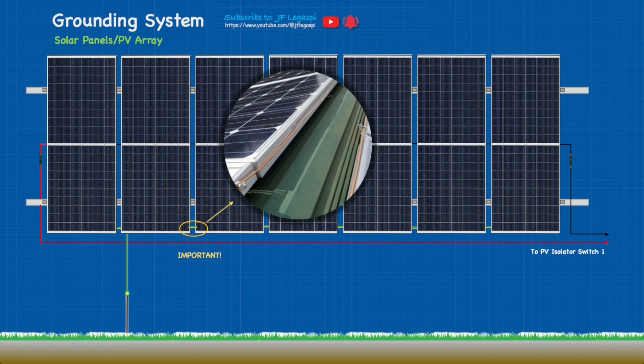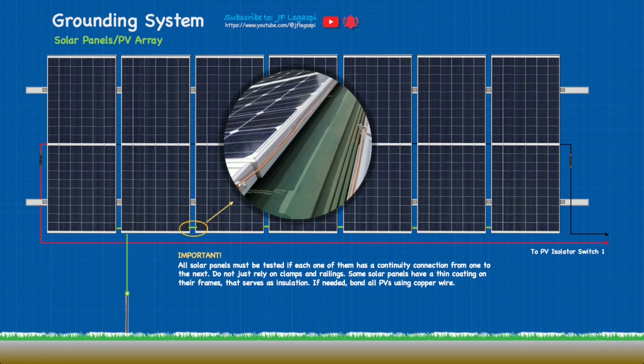And that is very important. All solar panels must be tested if each one of them has a continuity connection from one to the next. Don't just rely on clamps and railings, because some solar panels have a thin coating on their frames that serves as insulation. If needed, bond all PVs using copper wire. Now you don't have to do this if you are 100% sure that all the solar panels have continuity to each other.